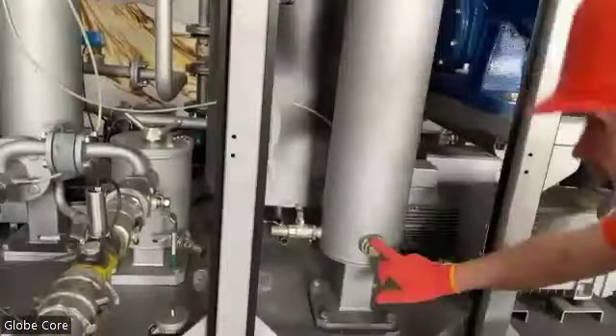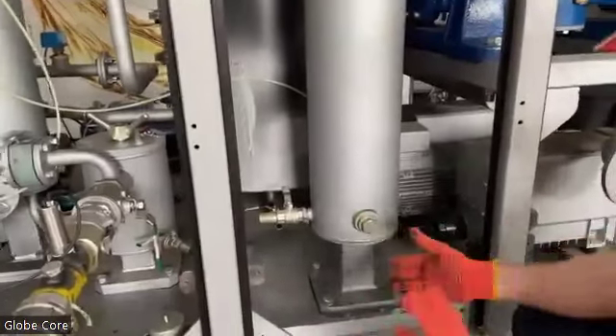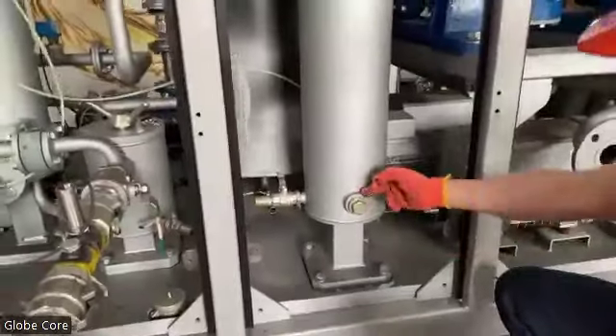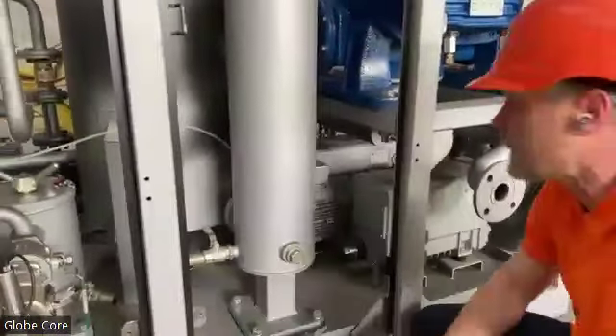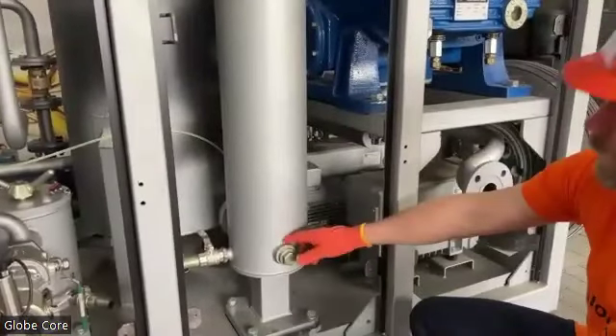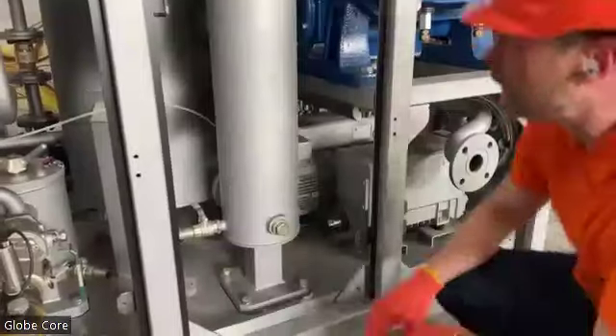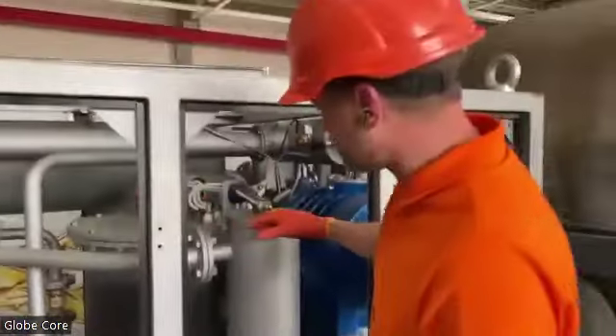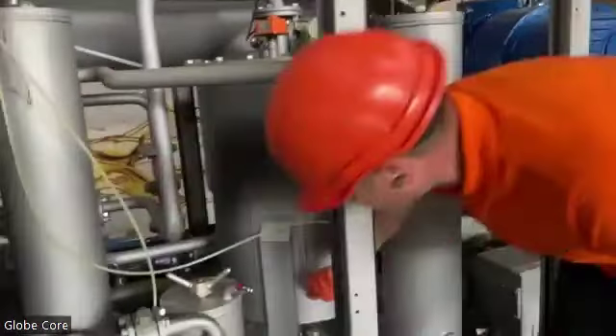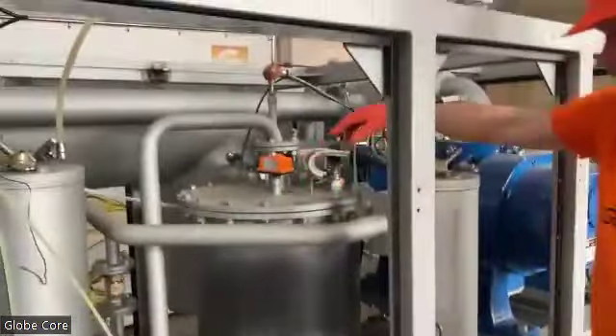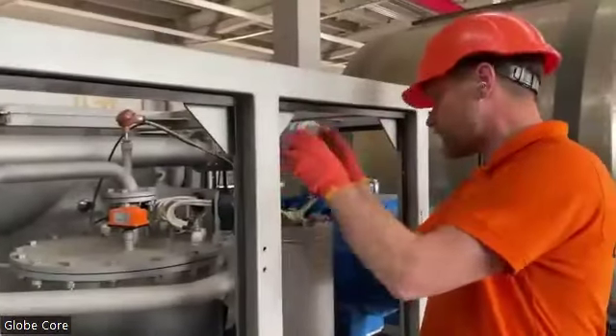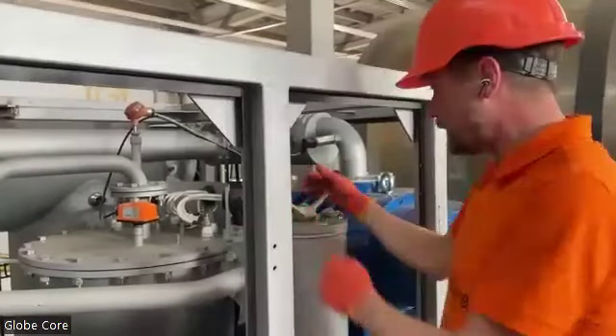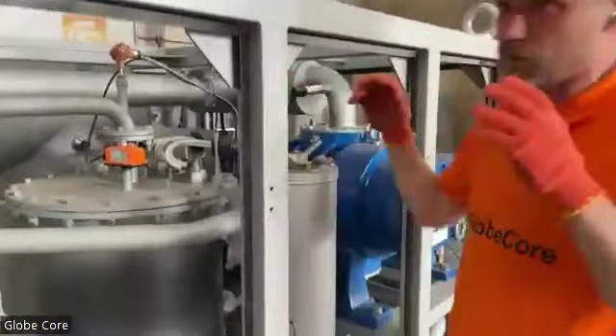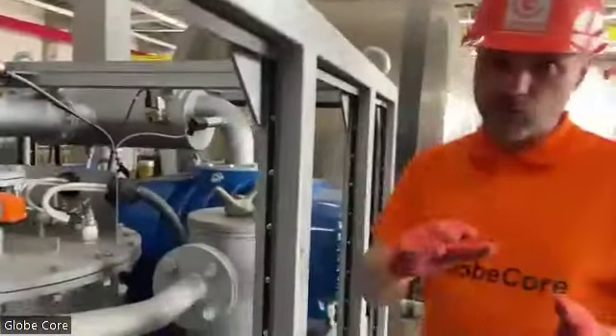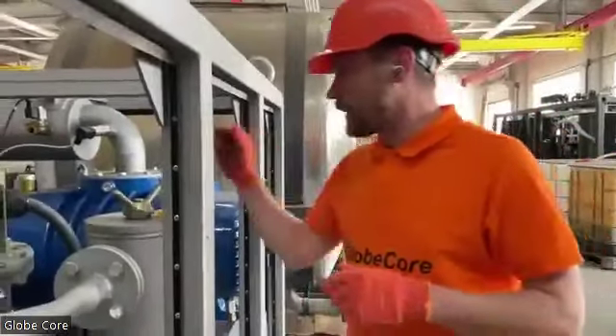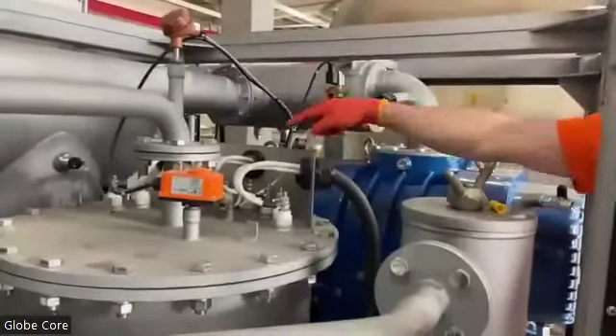Here, the magnets are placed. So periodically, the operators should take all this part and clean the magnets. So this is where the magnets are located in the filter. So after the filter, oil goes to the bottom of the heater. The heater in this design is located in a separate vessel. It has a total capacity of 150 to 180 kilowatts. We have 3 sections of the heater.